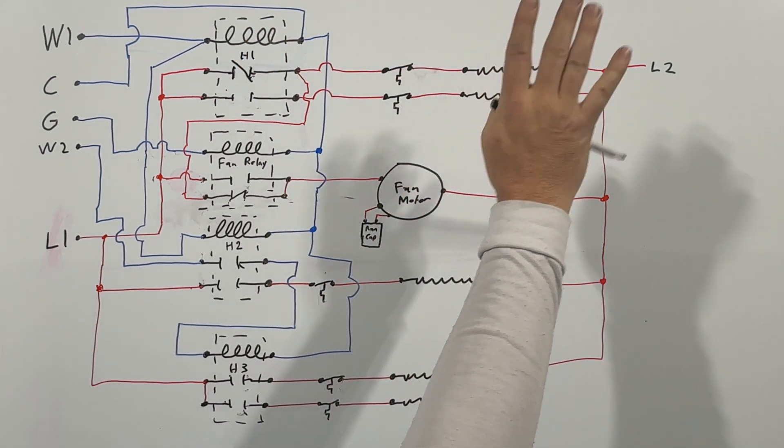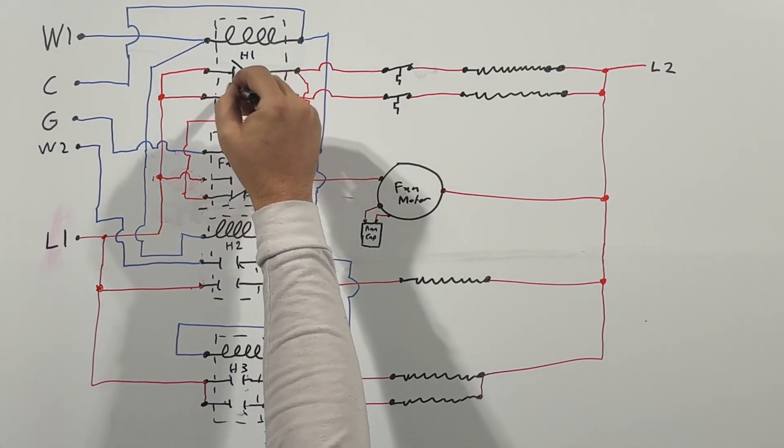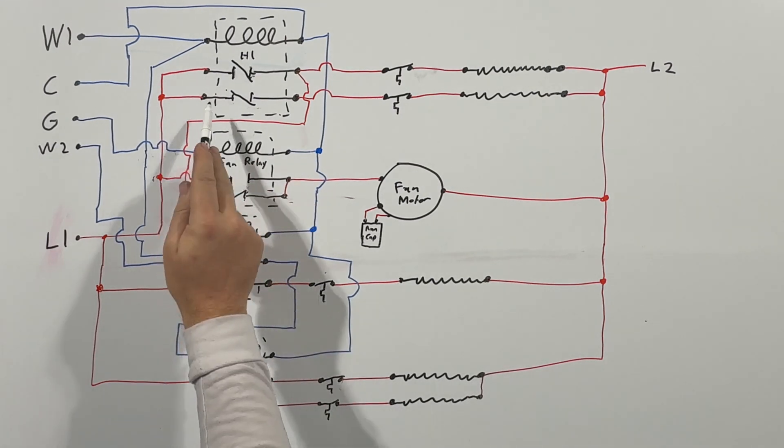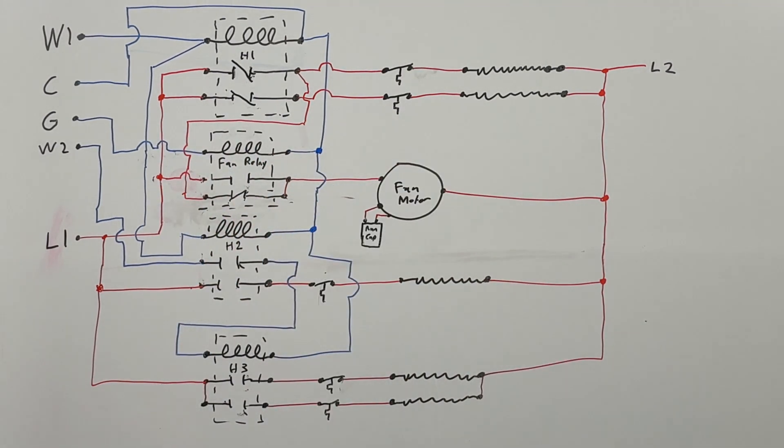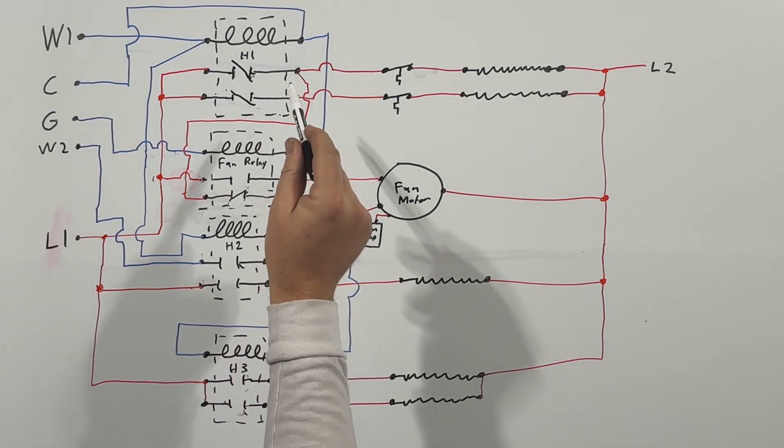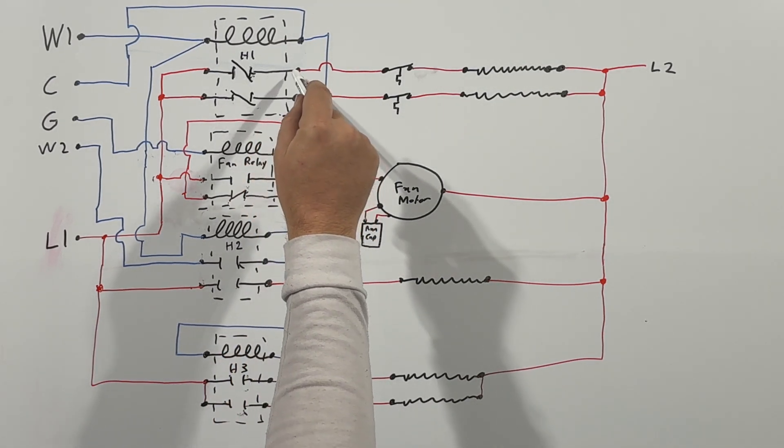Then going to L2, then our second contact will close. Same thing, it'll continue through and go through there. Alright, now I see that once this first contact closes, not only is the first heating element going to be energized, but we also have another high voltage line that feeds down to our fan relay.